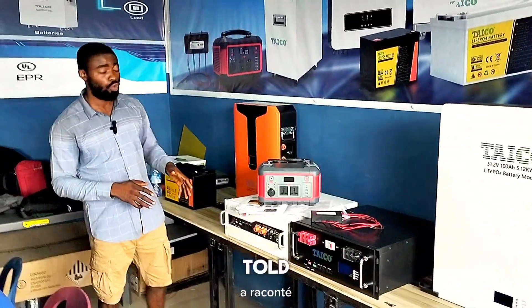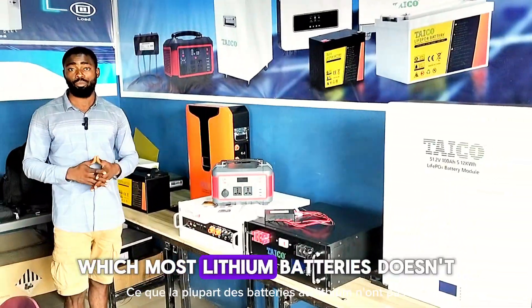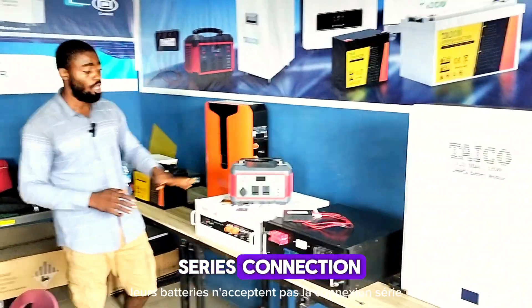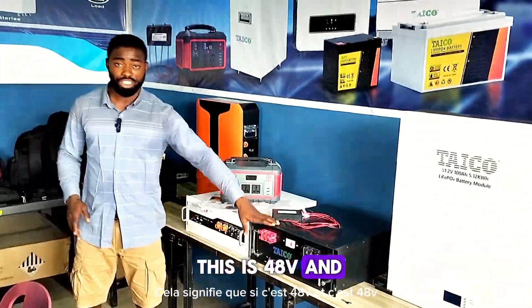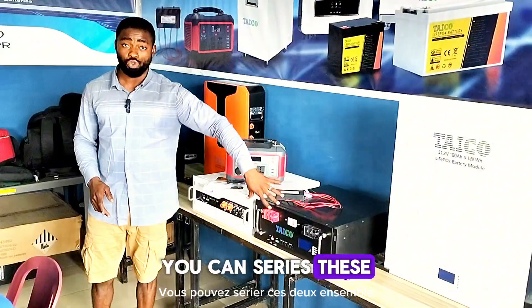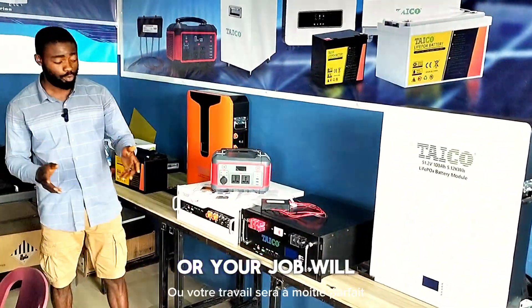One good thing about their product is that their batteries accept series connection, which most lithium batteries don't. Most lithium batteries tell you they don't accept series connection, but according to Taico, you can use their battery for series connection. That means if this is 48 volts and this is 48 volts, and you want to generate 96 volts, you can series these two together and your job will be perfect.